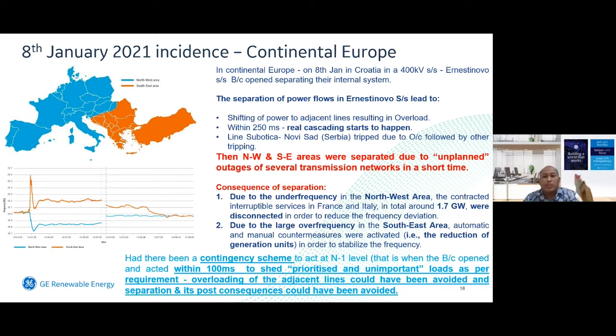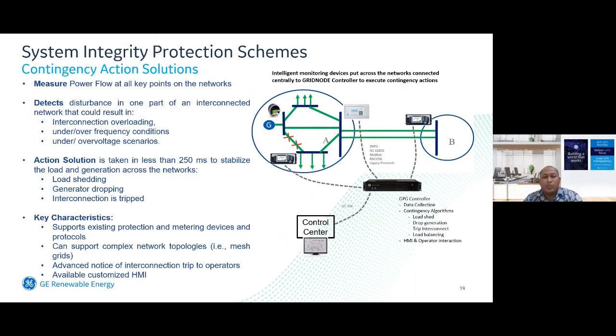So here we would like to highlight the solution that we have related to the example that happened in the Ernestinovo substation in Croatia. We call it the contingency action solution. The system works by measuring the power flow at all key points on the network, and then it detects a disturbance in one part of an interconnected network that could result in, for example, interconnection overloading, under or over frequency conditions, or under or over voltage scenarios. The action can be taken in less than 250 milliseconds to stabilize the load and generation across the network. The treatment itself could be load shedding or generator dropping, and as the ultimate solution, it can also be tripping the interconnection.